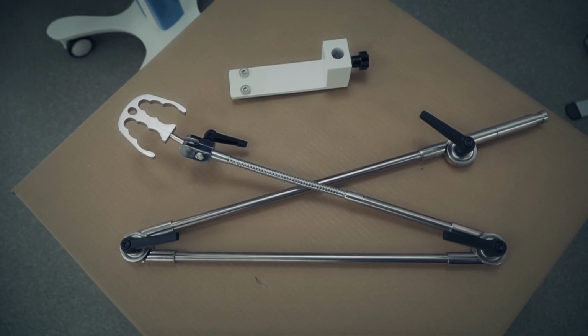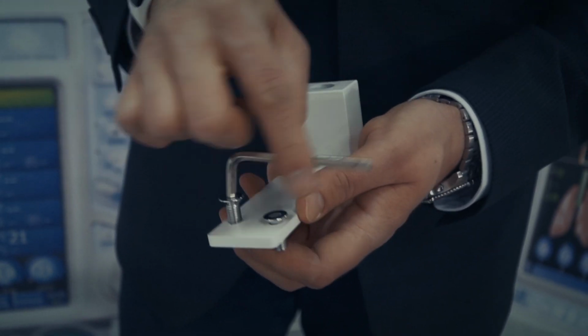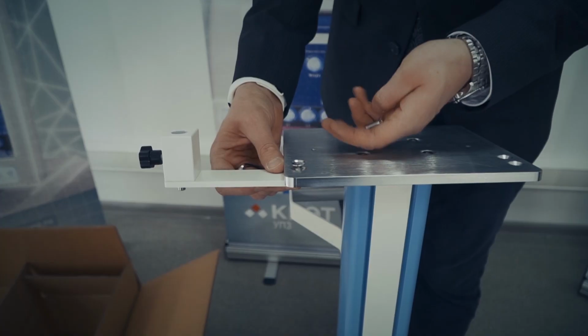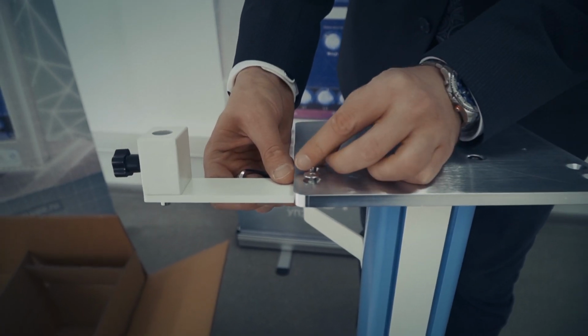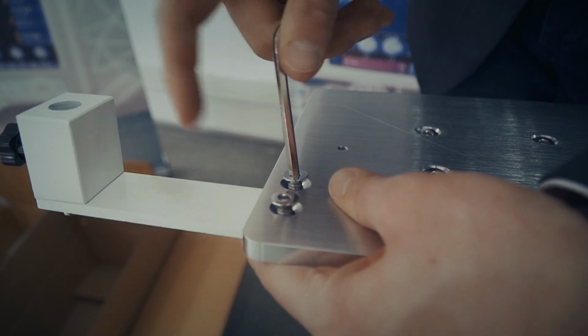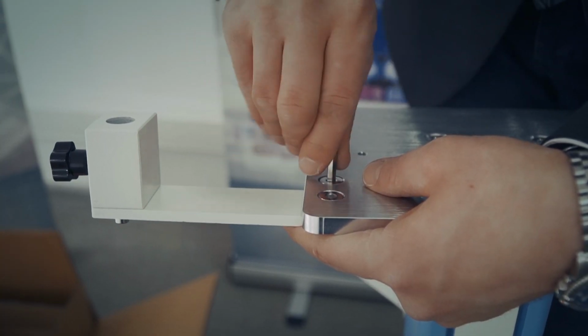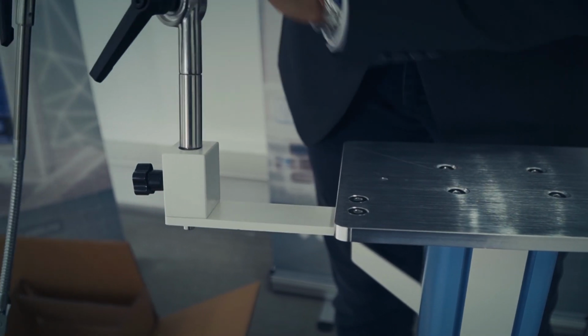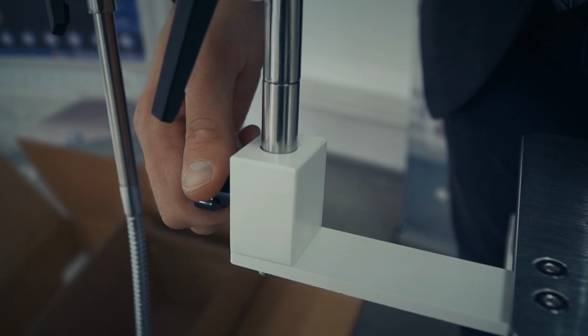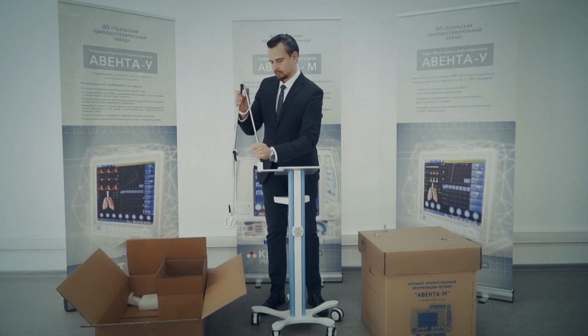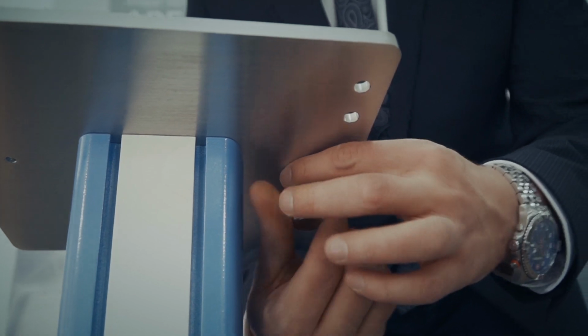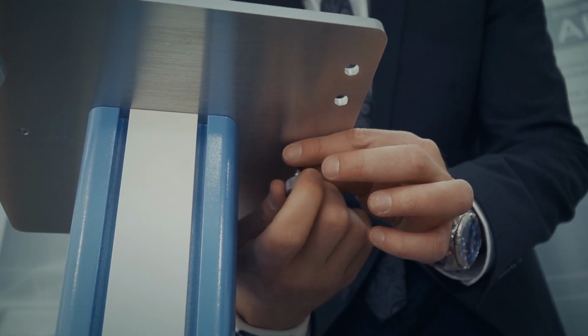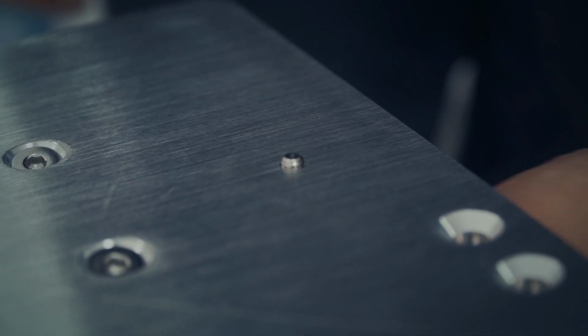Depending on the lung ventilator position relative to the patient, install fastener of the circuit holder either to the right or to the left of the platform. Fit the breathing circuit holder into the corresponding slot and secure it in this position. Now, screw in the screws fastening the ventilator body from the bottom of the platform. For convenient installation, the screw edge shall slightly project above the surface.